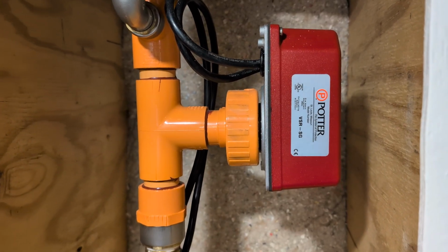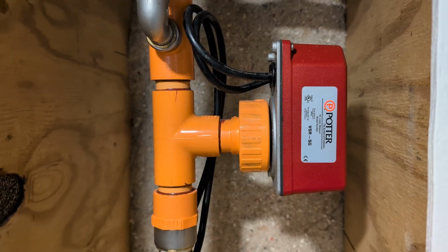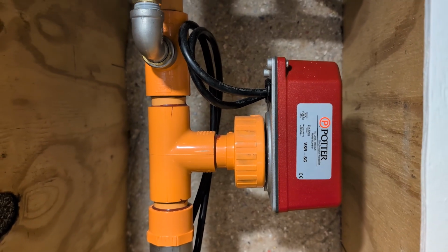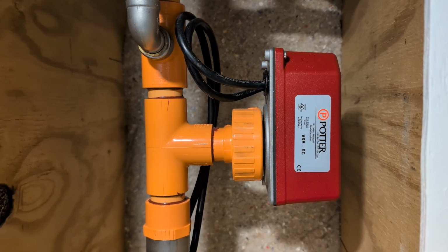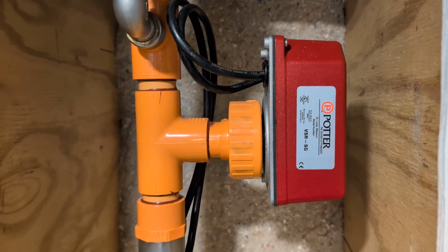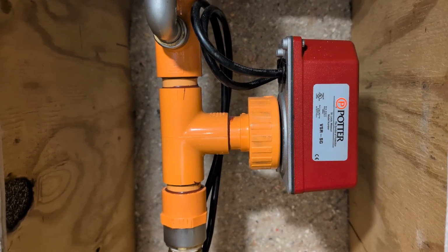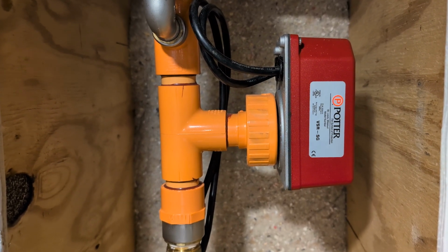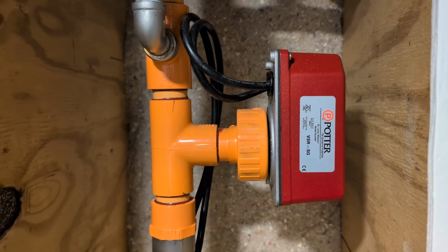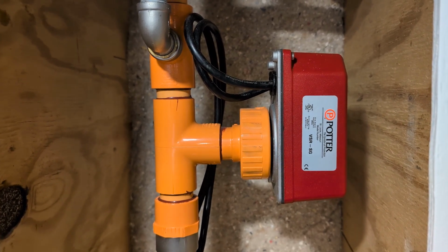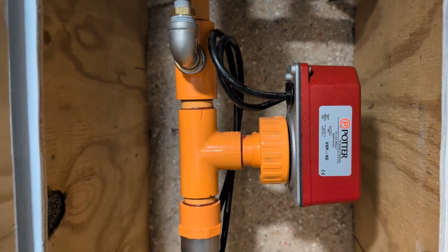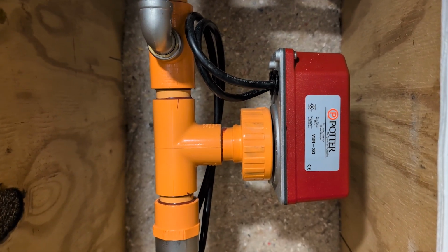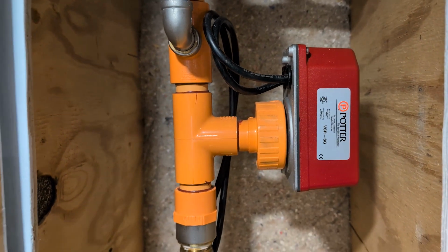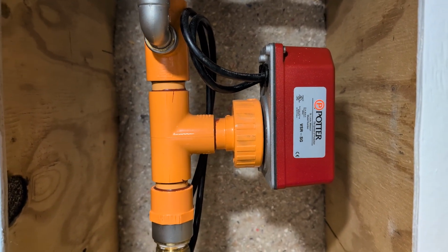We get asked, do we need a waterflow alarm for a home fire sprinkler system? The answer is no, you probably don't. If you have smoke alarms in your home per NFPA 72, which is the National Fire Alarm and Signaling Code, then you don't need to have a waterflow alarm installed. Again, the smoke alarms are going to be providing much more early warning than the waterflow alarm would be providing, so it is not required to be installed.